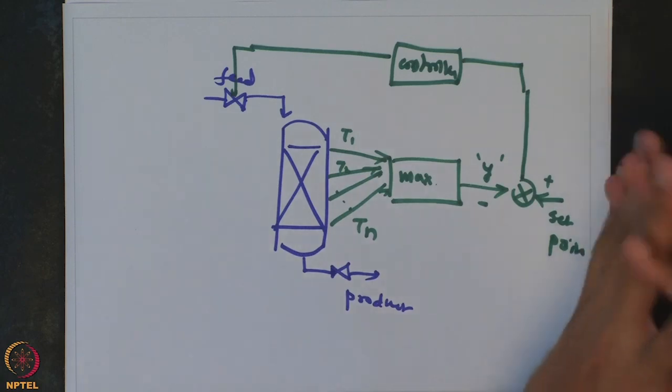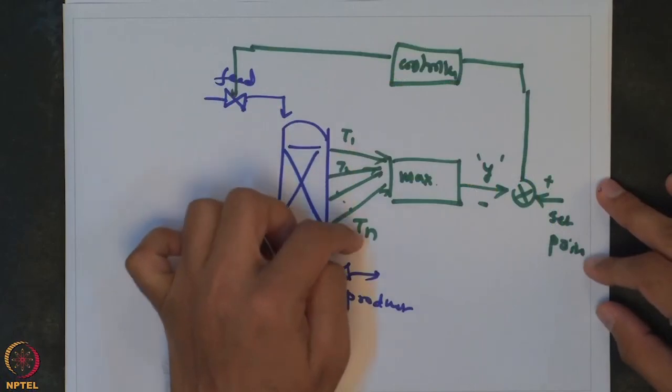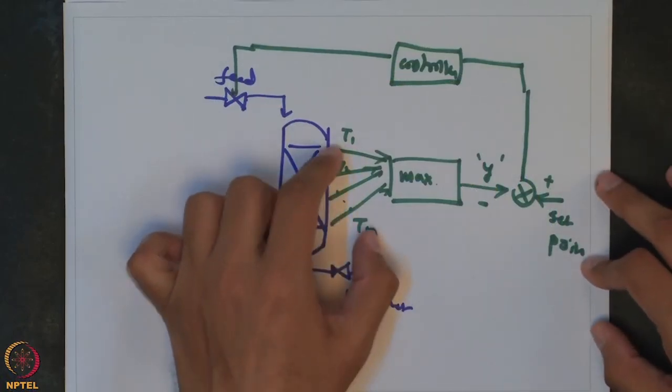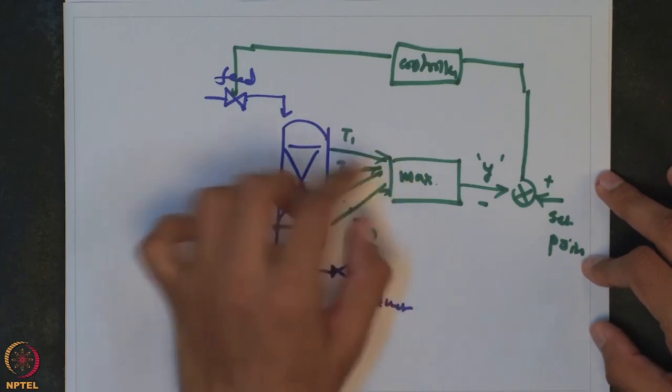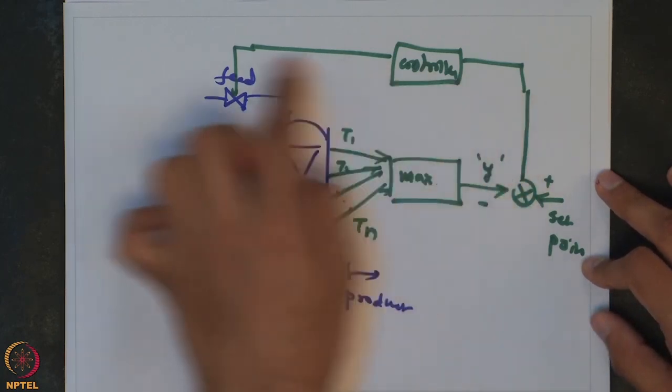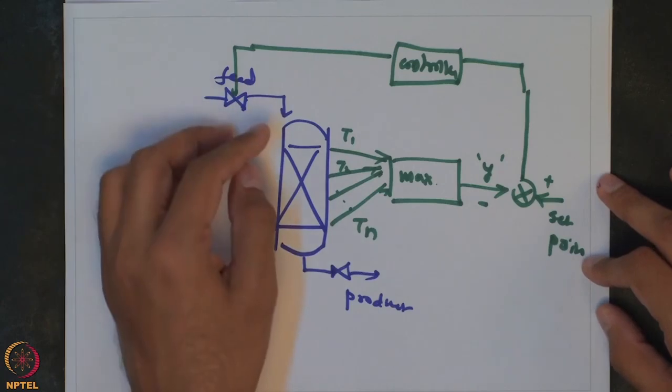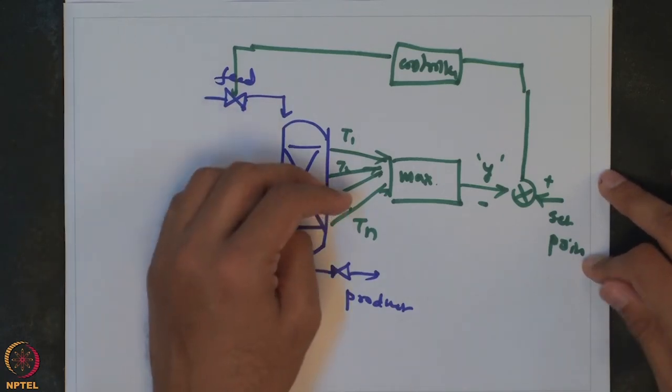This is an example of auctioneering control: we are using multiple measurements, but for each of those measurements we do not have a control loop. We select whichever is the critical measurement rather than a control loop and then take control action accordingly. That is the main difference between override control and auctioneering control, but both fall under selective control because we are selecting out of multiple possible control variables or measurements. This kind of strategy is very commonly used to control hot spot temperature in a fixed bed catalytic reactor.